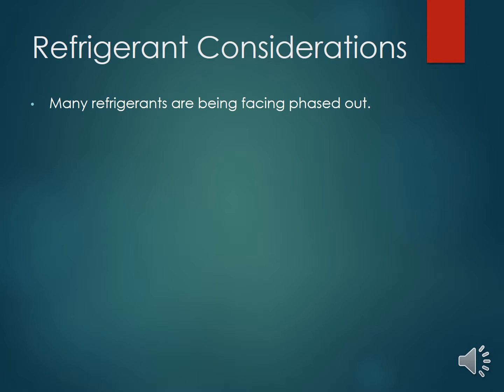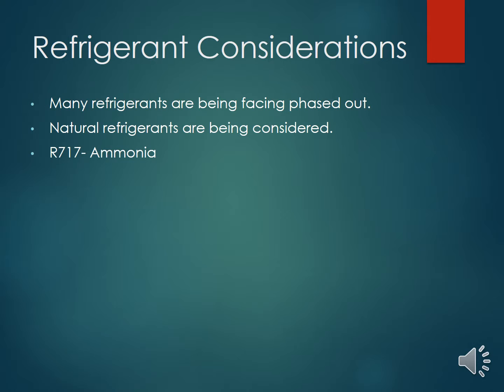Many of today's traditional refrigerants pose a threat to the ozone layer and also contribute to global warming. Some natural refrigerants are being looked at as possible replacements for these. All the natural refrigerants have their benefits and their inherent risk. Ammonia poses no threat to the ozone and has a very low global warming potential. The downside is its toxicity.